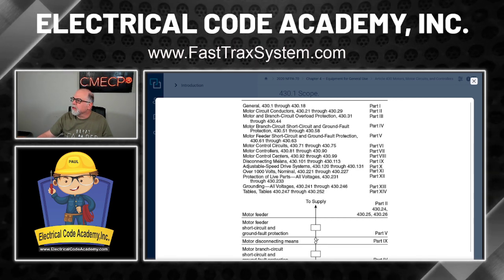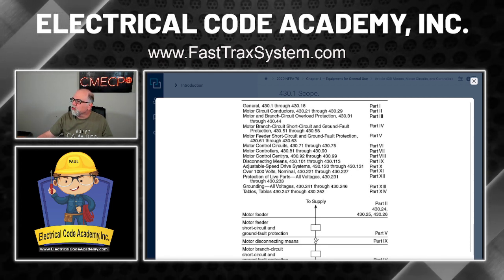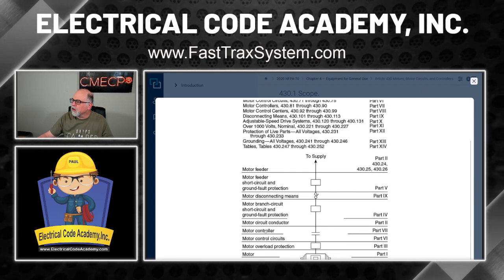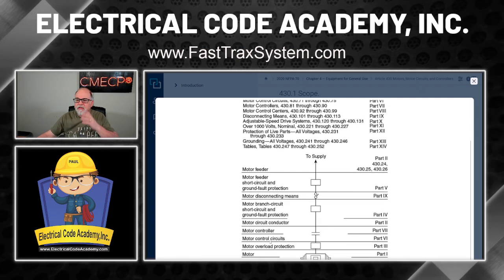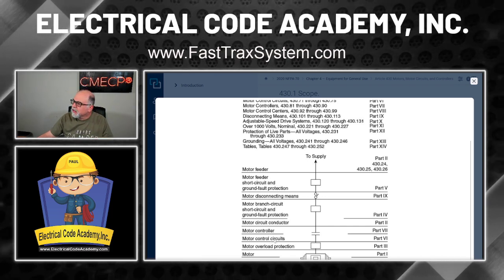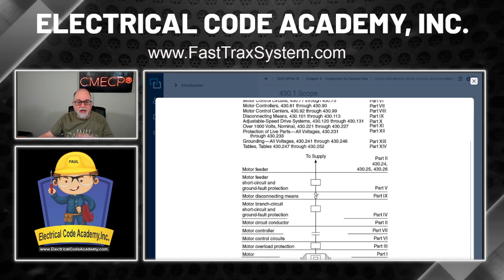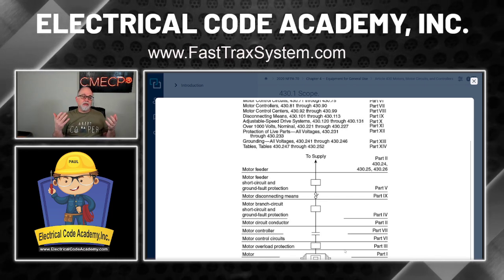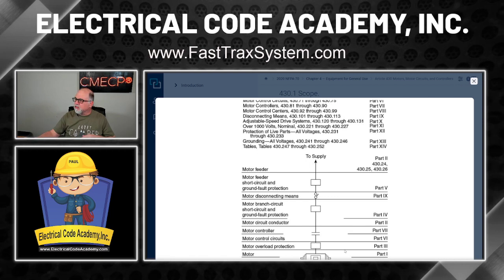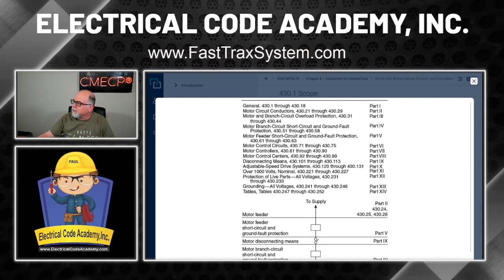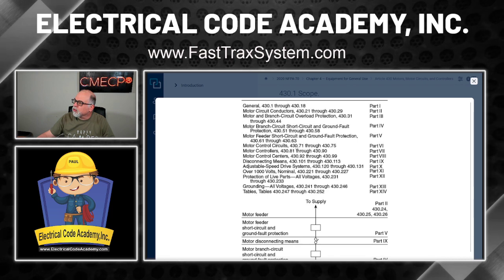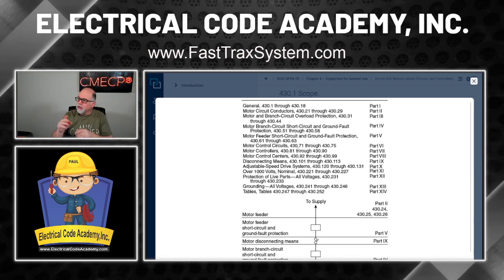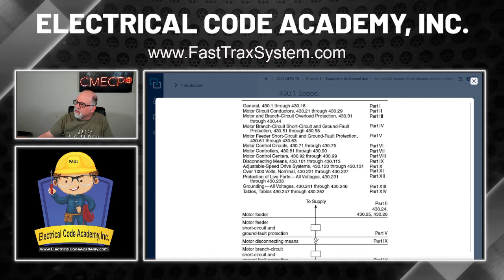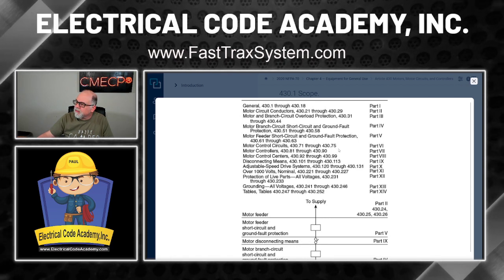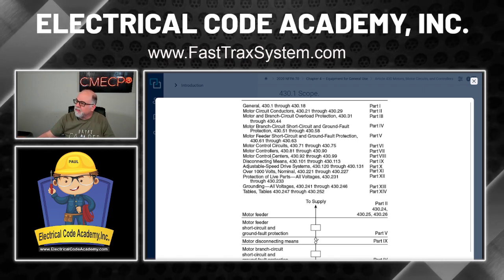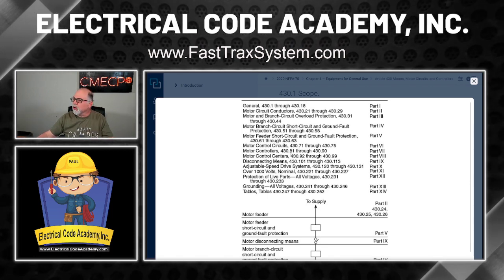All right, so here we're talking about, again, motor control centers. If you come down here, we're talking about motor control circuits right here. And that's what the question was, motor control circuits, right? And it looks like it is in part 6 of 430. So that's another good reason why you have these illustrations and this guidance. Now we can verify that by going up here and looking also here. Notice it says motor control circuits, and this can be a huge shortcut for you because it's going to tell you that you can start at 430.71 and it goes to 430.75. And we'll see if that helps us. You also have disconnecting means down here, but we're going to see what it is here.